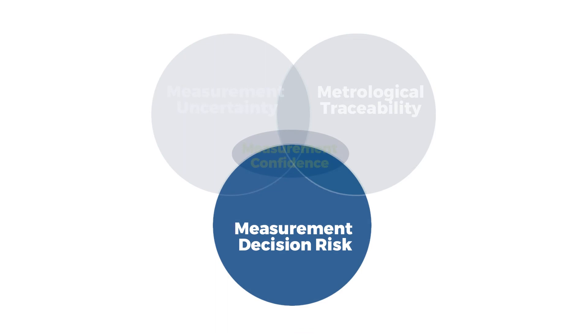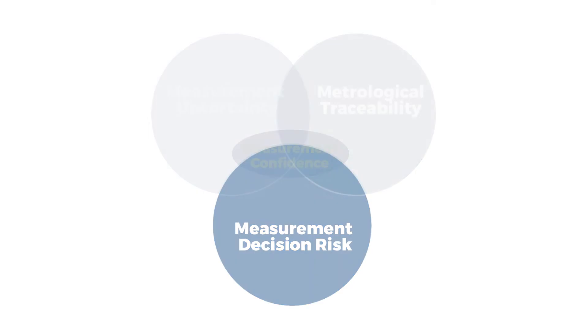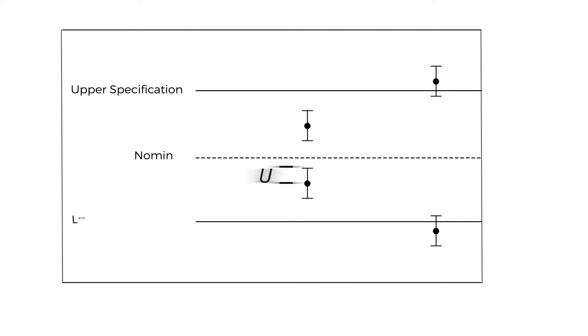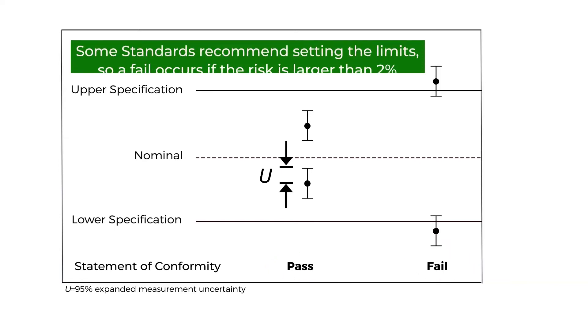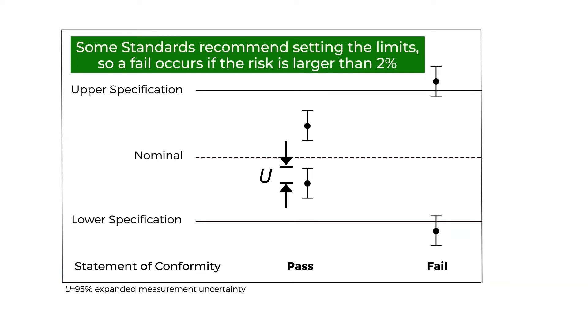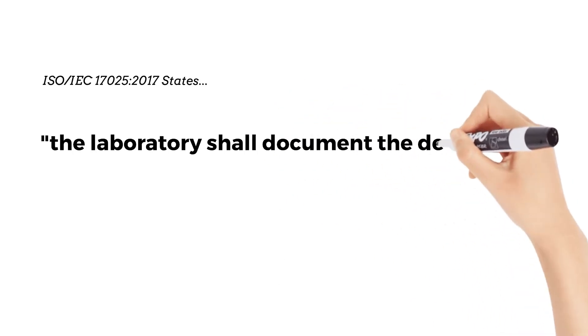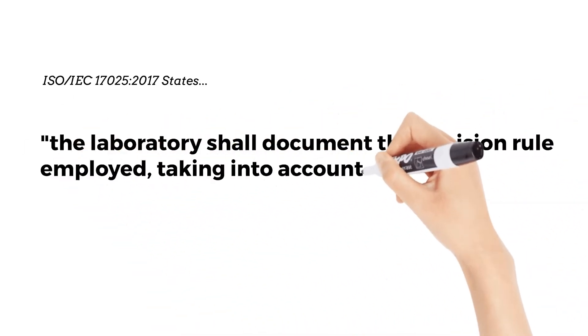Measurement decision risk focuses on understanding decision risk and TUR. When discussing decision rules, we describe how measurement uncertainty is accounted for when stating conformity with a specified requirement. The conformity for most is binary, meaning either a pass or a fail, and some standards recommend setting the limits so a fail occurs if the total risk is larger than 2%. The laboratory shall document the decision rule employed, taking into account the level of risk.